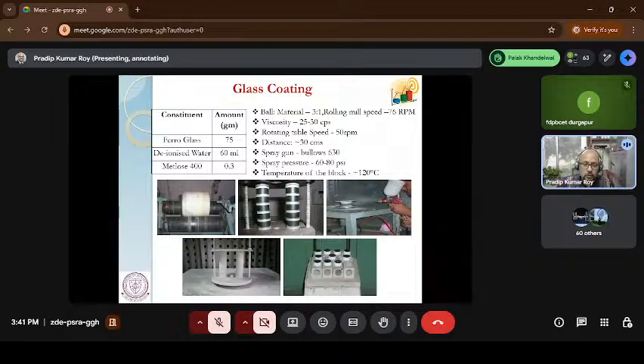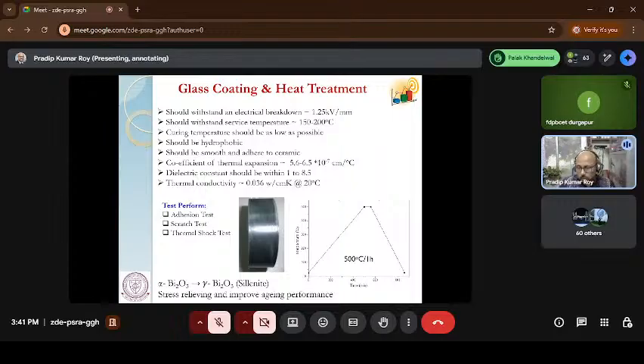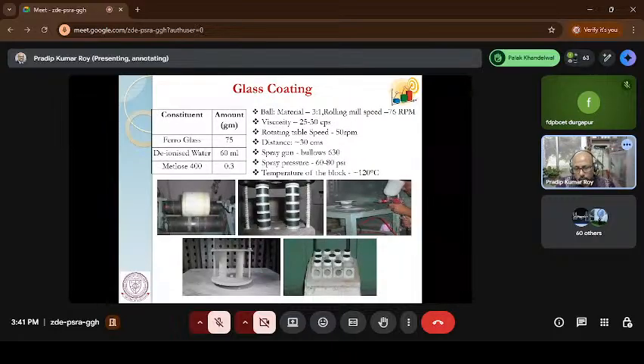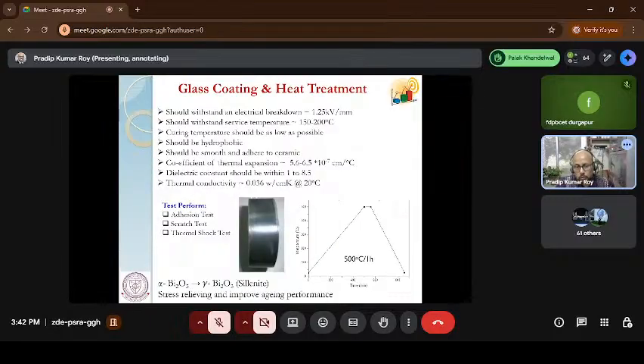After coating, they matured it at a certain temperature, around 500 to 600 degrees Celsius. You can look here, the glass looks white, this is the green glass. After maturing it becomes completely transparent. Then we do testing here, like adhesion testing, scratch testing, thermal shock testing. These tell how well the glass adheres to the ceramic body. That is very much required, because if any gap is there between the body and the glass, there is a high chance that flashover happens through that gap.